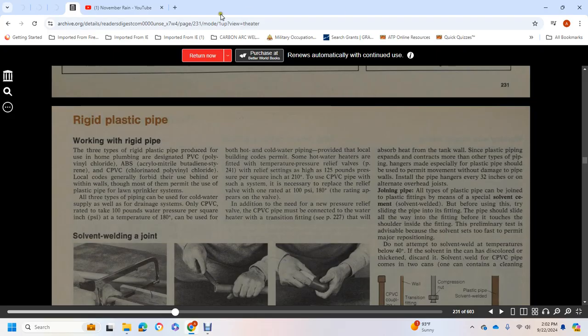Rigid plastic pipe. Working with rigid plastic pipe. The three types of rigid plastic pipe provided for home plumbing are designated polyvinyl chloride or PVC, ABS or acrylonitrile butadiene styrene, and CPVC or chlorinated polyvinyl chloride. Local codes generally forbid the use of plastic behind or within thin walls, though most of them permit use of plastic pipe with lawn sprinkler systems. All three types of piping can be used with a cold water supply as well as drainage systems. The chlorinated CPVC, rated at 100 pounds per square inch at a temperature of 180 degrees, can be used in hot and cold water piping where permitted by the local building code.